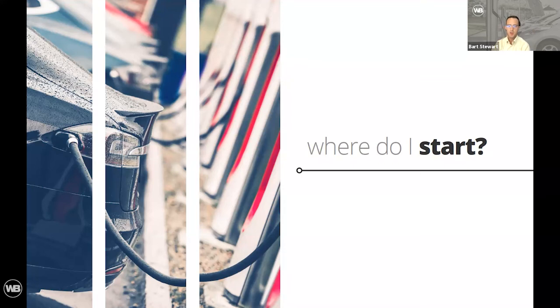Installing a small amount of level 2 chargers is straightforward. A growing number of groups can give you a solid lump sum fee based just on a narrative and a sketch. Once you're talking fleet applications or level 3 installations, we recommend some engineering design before pricing, to make sure you get competitive apples-to-apples pricing. Past one or two level 2 chargers, you'll need permit drawings, site plans, and zoning approvals from your local permitting authority. One or two level 2s is something an electrician would pull a trade permit for, typically without needing a lot of drawings.